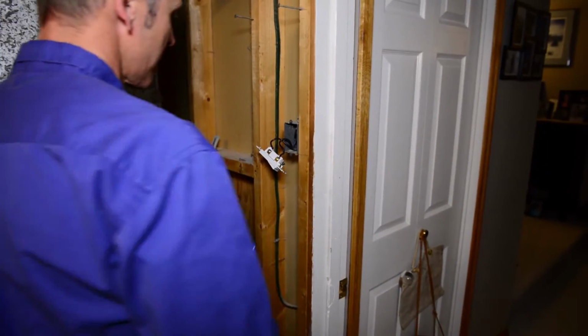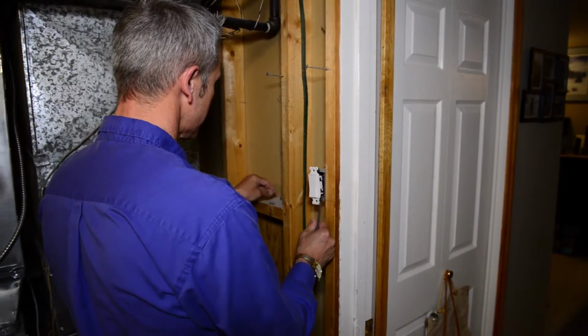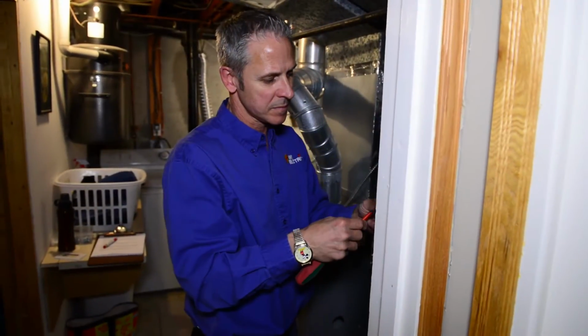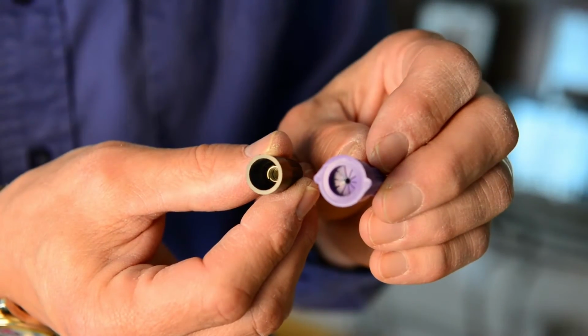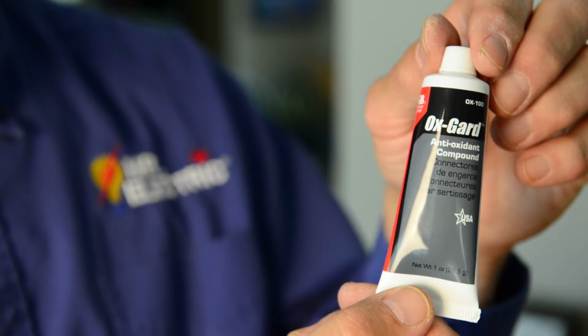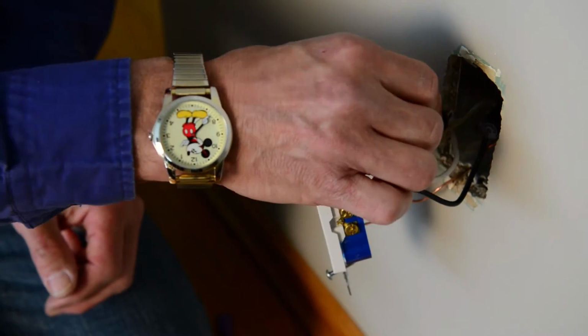If you do have aluminum wiring, an electrician can go through your entire house and open up all the switches and joints and tighten them all to mitigate the risk of fire. Furthermore, an electrician can tell you if the proper aluminum marrettes were used or whether a special product called Penetrox was applied to ensure the aluminum connections were properly treated. The marrettes are used to safely join wires from your circuit to your device, like a switch or a plug.